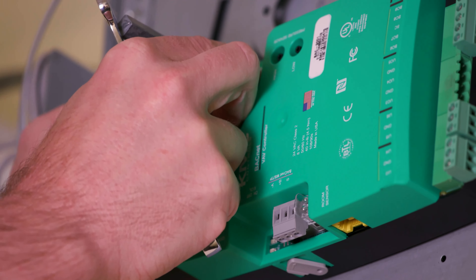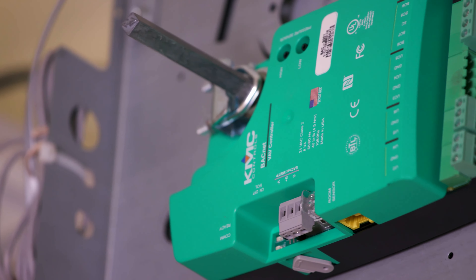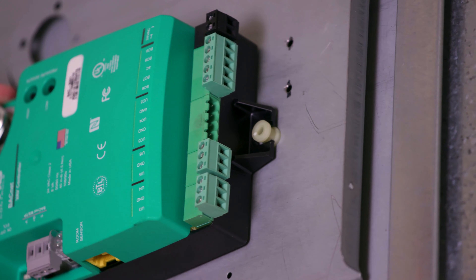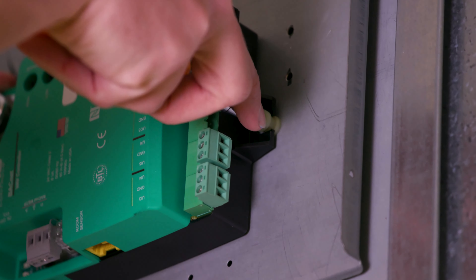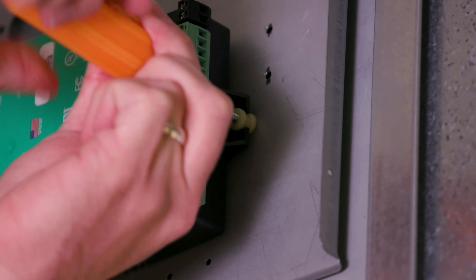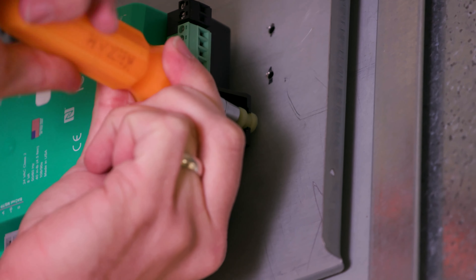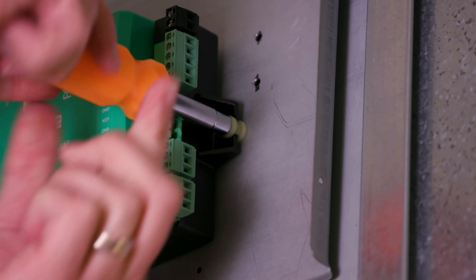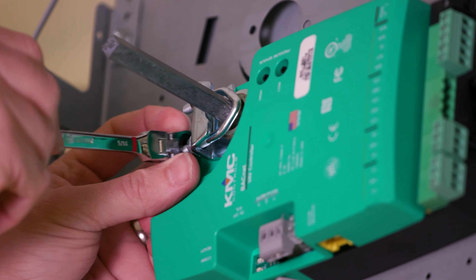Finger tighten the V clamp nuts to hold the damper shaft in the drive hub. Next, locate the white mounting bushing, which is held by the mounting tab at the bottom of the controller behind the terminal blocks. Center the mounting bushing in the mounting tab and attach the controller to the VAV terminal box using a number 8 sheet metal screw. Finally, evenly tighten the V clamp nuts on the drive hub to 30 to 35 inch pounds.